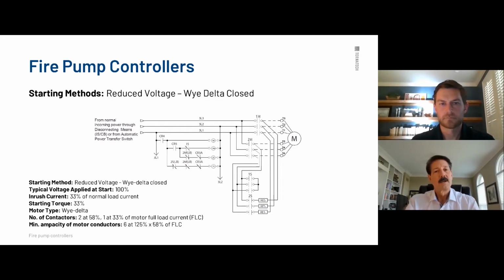I'll move a little quicker here. Wye delta closed? Here's your resistors. Very simple. What we do is we have reduced voltage, and it's running through a set of resistors, which reduces the voltage, as you see, into the motor itself. And then we transition. Primarily what happens with the resistors, again, they stay in the circuit. And it's called a closed transition. So the motor leads never, ever, ever have an open circuit, an open voltage, or I should say no voltage. What's happening is those resistors stay there, so there's a constant voltage that's applied to the leads of the motor itself, closed transition, obviously. And the reason why, I'll show you the next slide that'll explain that.